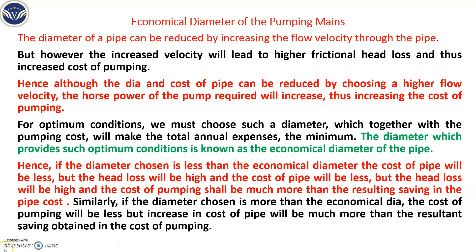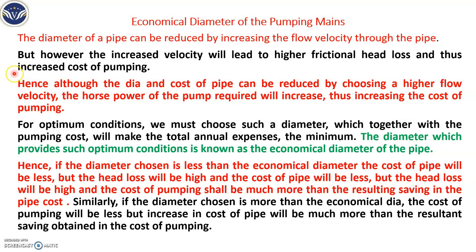So what happens when you reduce the diameter of that pipe? When you reduce the diameter, there is an increase in the flow velocity. When there is an increase in flow velocity, it increases the cost of pumping. Although the cost of the pipe is reduced by choosing a high velocity, it increases the horsepower requirement, and thus it increases the cost of pumping.